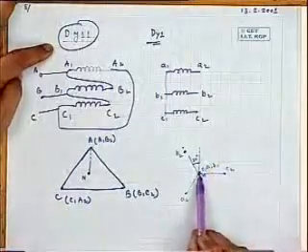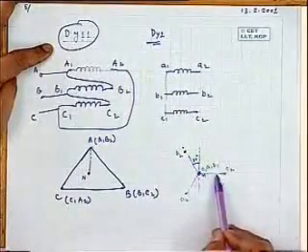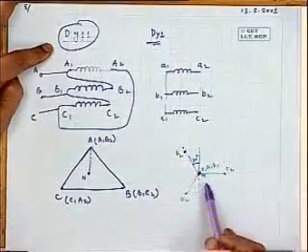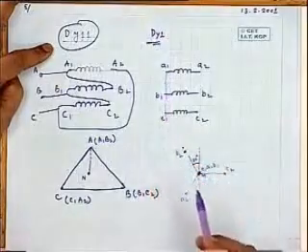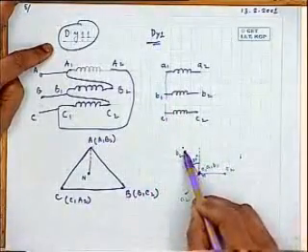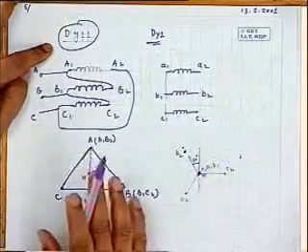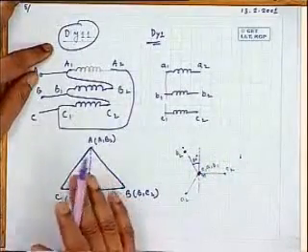So one of the ways you connect. Give supply like this. You get this voltage. Then, looking at your requirement, you try to connect the secondaries. So I wanted to do Dy11. I find, okay, nice, secondary voltages I wanted to have here, here, here. And these voltages are available. And accordingly I place them and connect them. But the only problem with this connection is with the marking of the terminals.